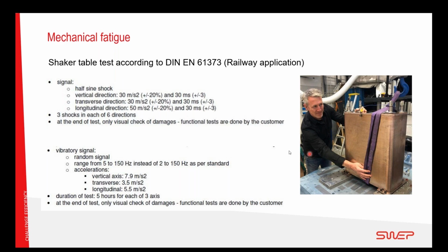So here was a shock and vibration test, and the vibrations are going from 2 up to 150 Hertz, and the amplitude of the acceleration is also defined by the test, and that's 5 hours in each of the axes. So basically this is a test where we make sure that there's no malfunction of the heat exchanger, but also that there's no separation between the heat exchanger and the connection plates, so that the heat exchanger is secured.